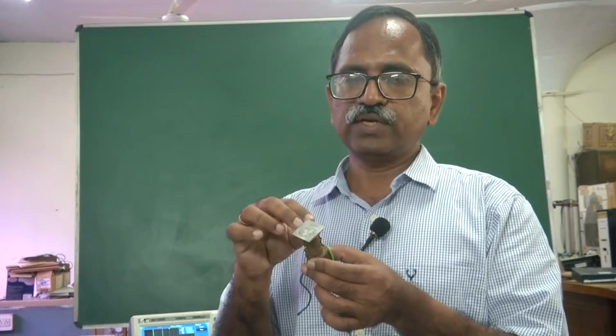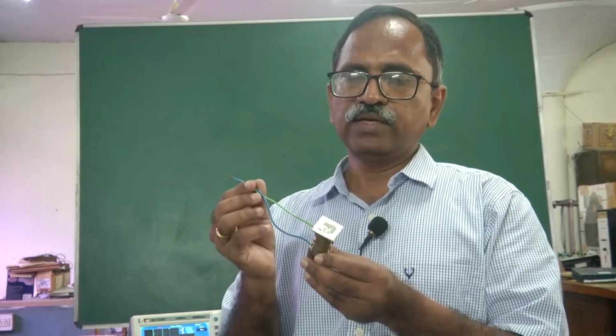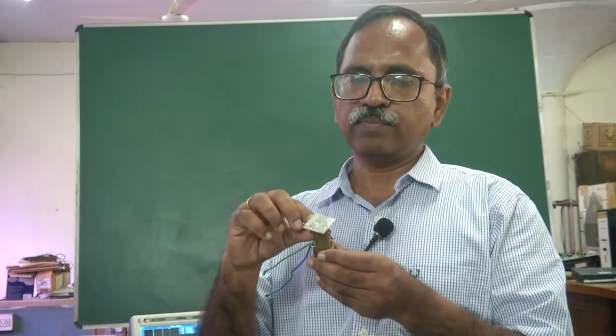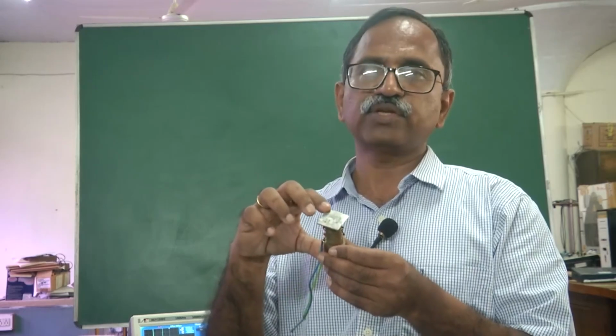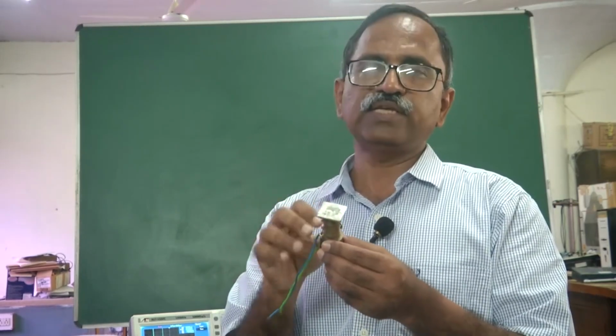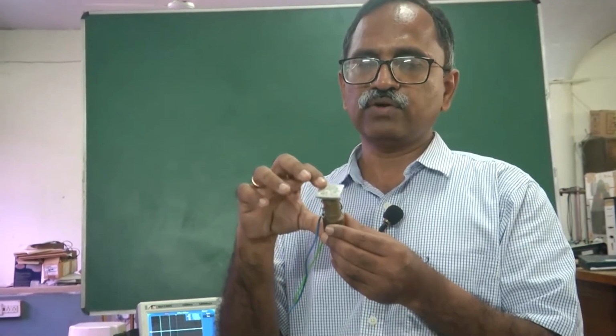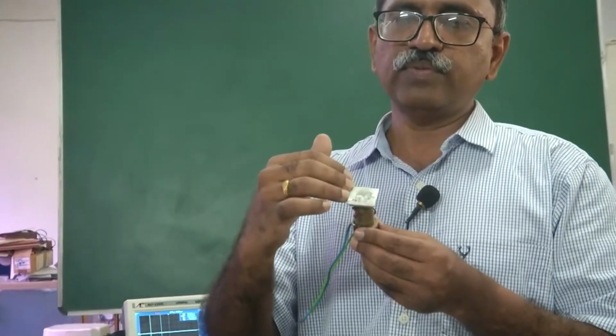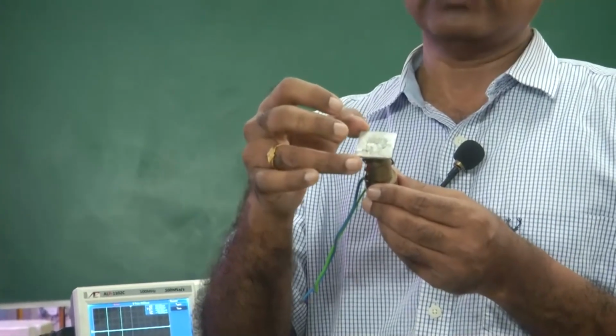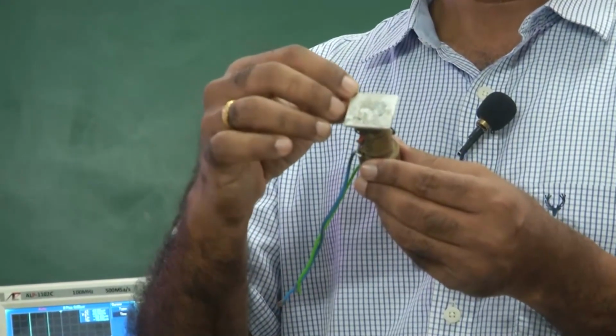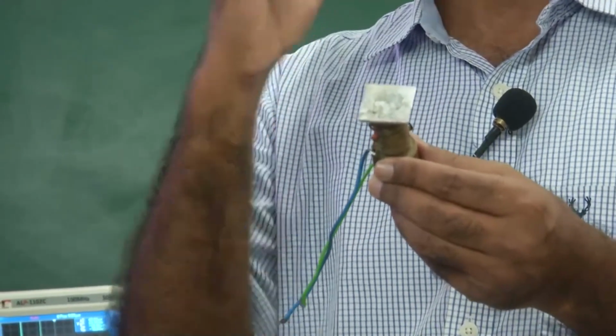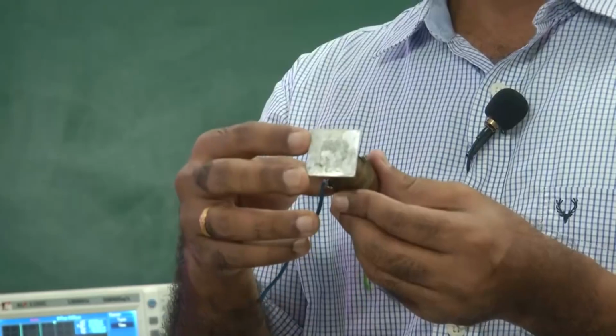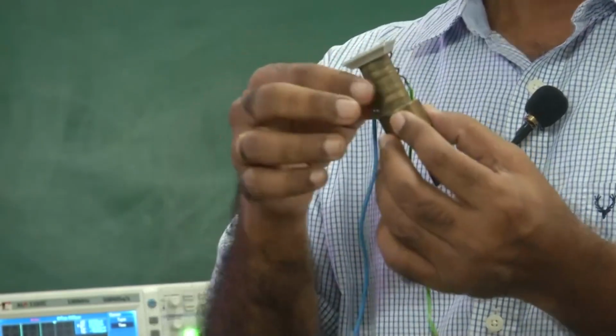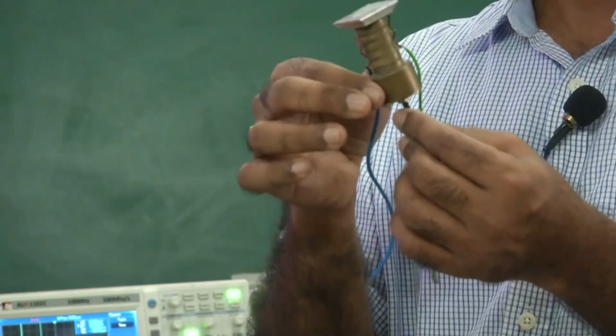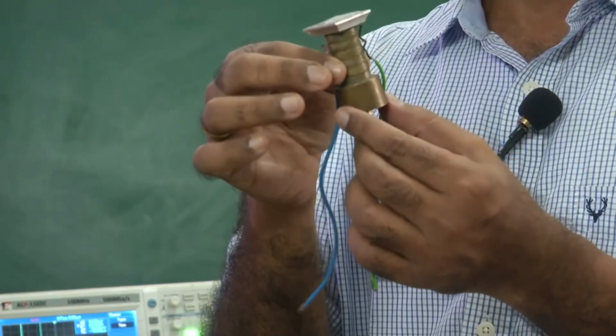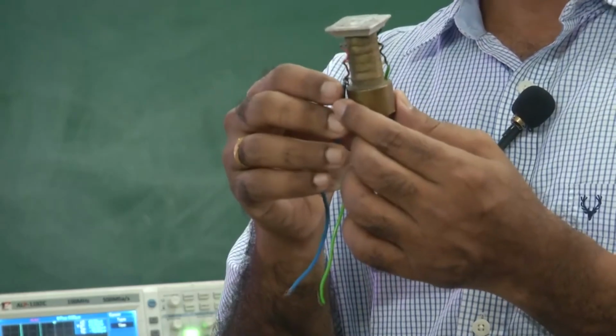the signal. So, this transducer is fed with a signal, and the signal basically is fed at a frequency which is the natural frequency of the transducer. So, when you feed the signal which is the same as the natural frequency of this transducer, then the output vibration from the face or the head of this sensor, the amplitude is large enough, and then you have a strong signal which is radiated out. The reflected wave is also sensed using this particular sensor. So, the objective in today's experiment is to find out the natural frequency of this sensor by detecting the resonant condition, right.